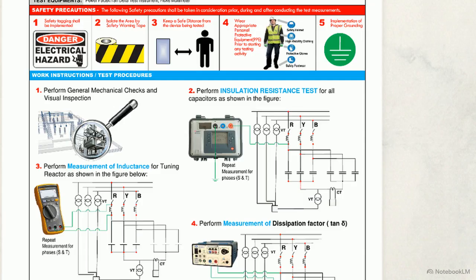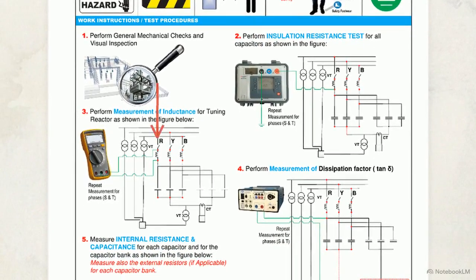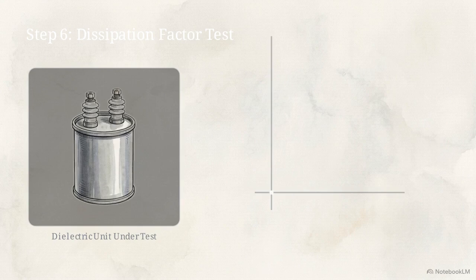Step 4 is the insulation resistance test for all phases. After each DC megger measurement, units are discharged to clear dielectric absorption charges. In Step 5, tuning-reactor inductance is measured. Readings must meet exact tolerances to prevent unwanted harmonic resonance. Step 6 is the dissipation factor test. By measuring the ratio of resistive to capacitive current, engineers evaluate internal dielectric purity.